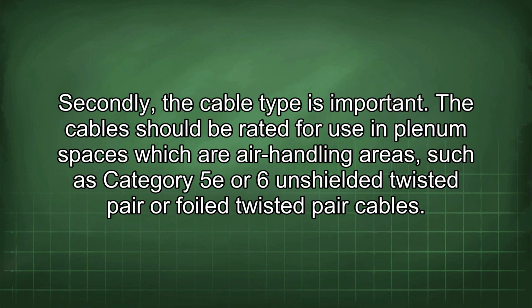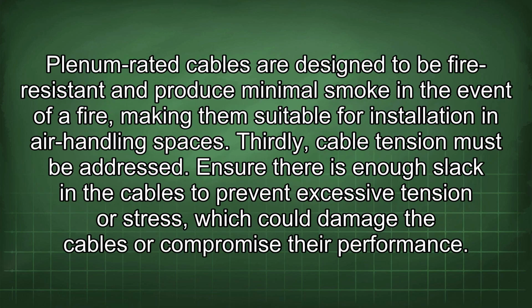Secondly, the cable type is important. The cable should be rated for use in plenum spaces, which are air handling areas, such as Category 5E or 6 unshielded twisted pair or foiled twisted pair cables. Plenum rated cables are designed to be fire resistant and produce minimal smoke in the event of a fire, making them suitable for installation in air handling spaces.